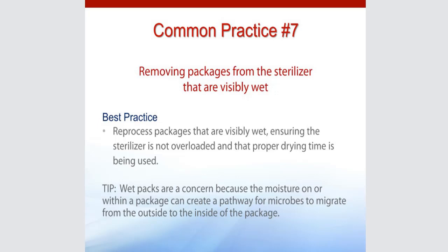Okay, we're rounding the corner and we're on to common practice number 7. Removing packages from the sterilizer that are visibly wet. Wet is wet. It's not kind of wet. It's not just a little wet. If it's wet, it's not dry. And so you should not touch any instrument pouch or package that is damp, visibly wet, because there is the chance that whatever is on your hands or on the countertop that you might set it on, those fibers are still wet and they're separated, and you can have wicking or a transfer of the contamination from your hand or the countertop into the sterilization pack.